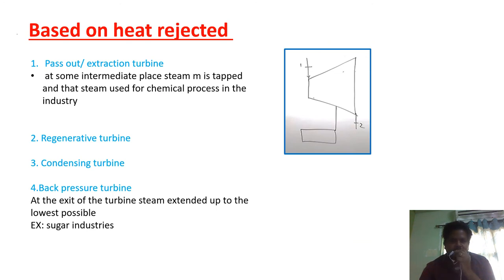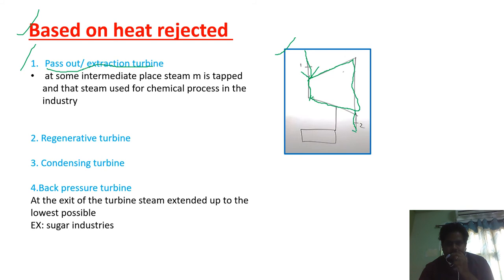The other classification is based on heat rejected. The first type is the pass-out or extraction turbine. Steam enters the turbine at point 1 and leaves after expanding through the turbine at point 2. In the pass-out or extraction turbine, at some intermediate place before full expansion, some amount of steam is extracted and used for industrial processes. This is called a pass-out or extraction turbine.